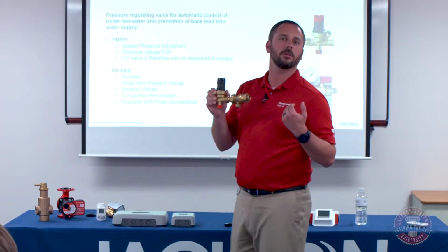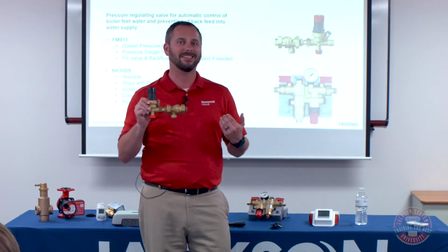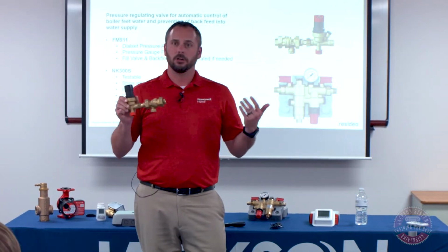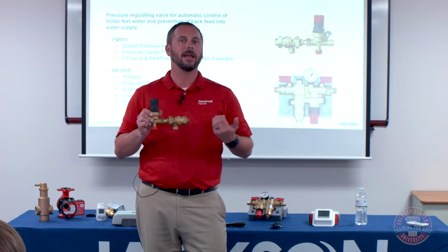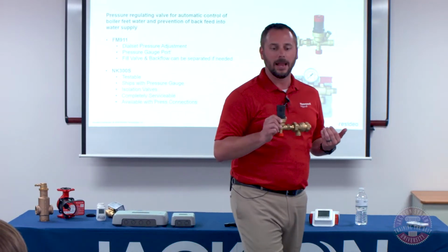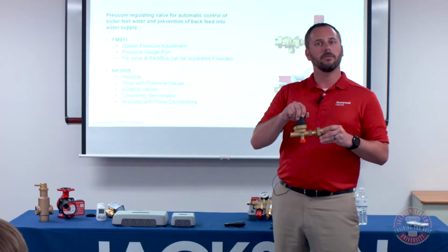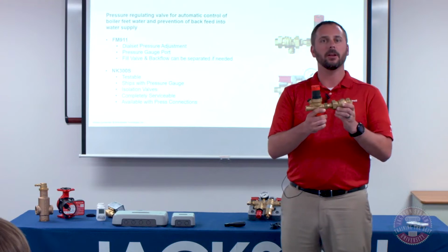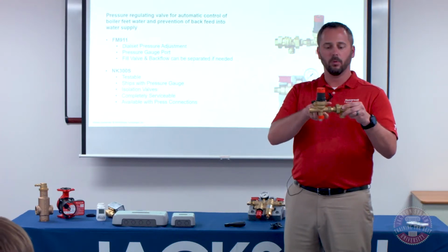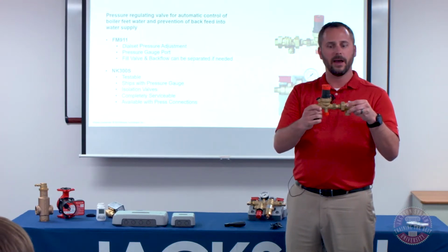This prevents any of your hydronic heating water that's been sitting stagnant in the lines for, could be 5, 10, 15 years, from ever making its way back into the drinking water supply. And then we also have a fill valve, which are typically married together, although some people will put a bypass around here for faster filling.